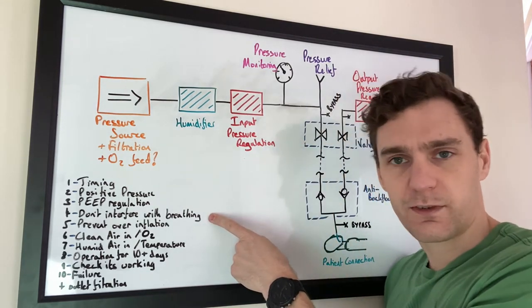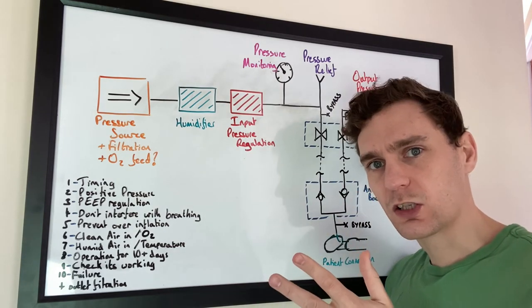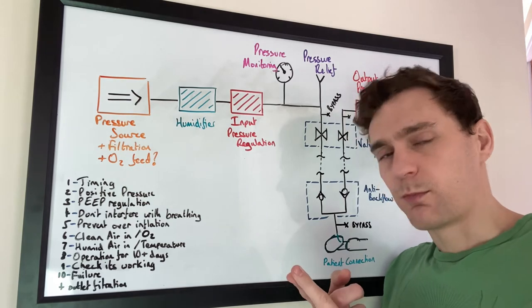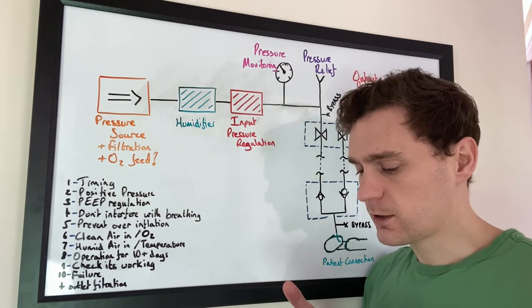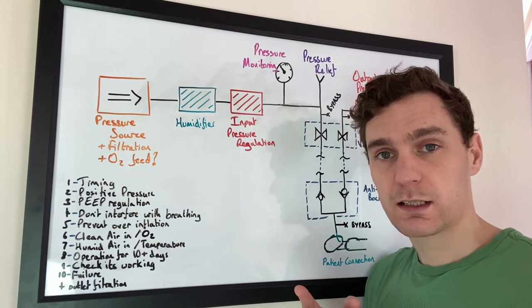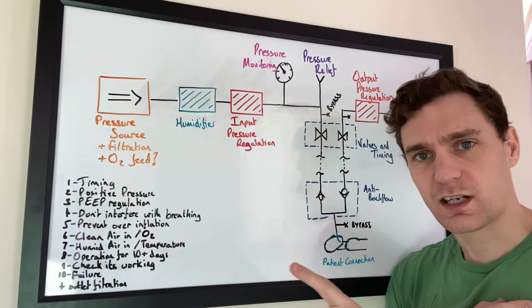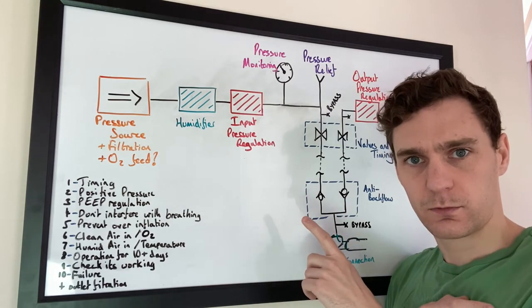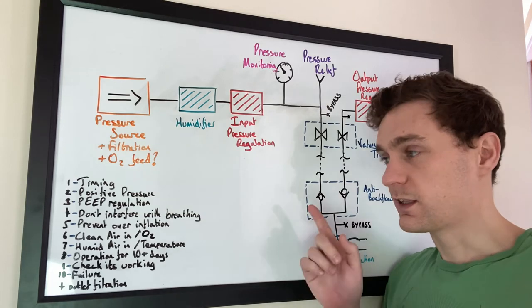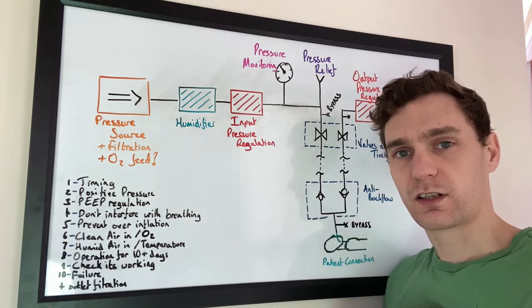Fourth thing, don't interfere with breathing. I mentioned in the last video there are three ways that you can do this. You can apply drugs, either paralytics or sedatives to suppress lung function. You can detect breathing rate or you can have some other means. This system has no sensing on it which feeds back from the patient to the system. Therefore this has to be used in conjunction with appropriate drugs so that the lung function is suppressed.